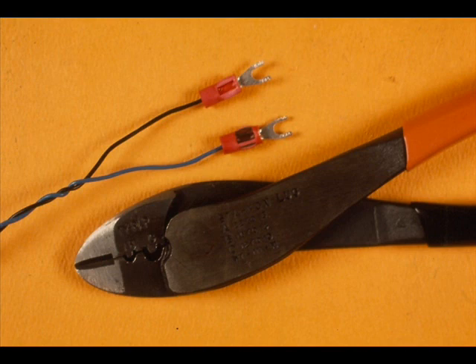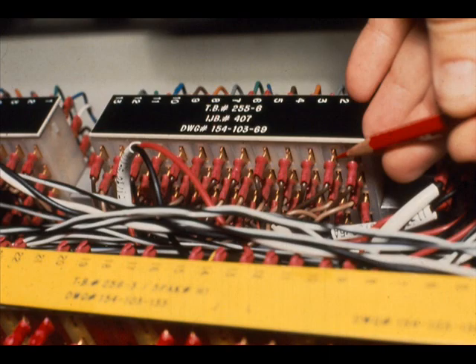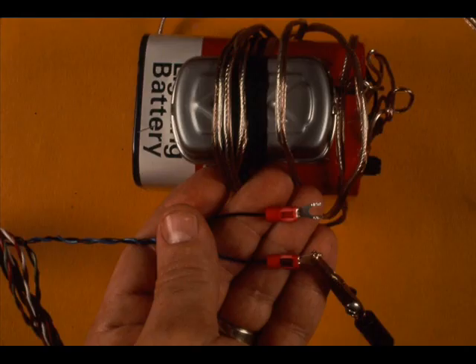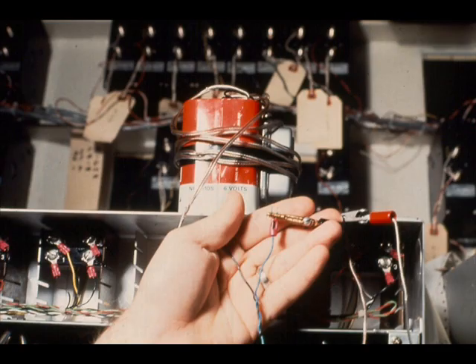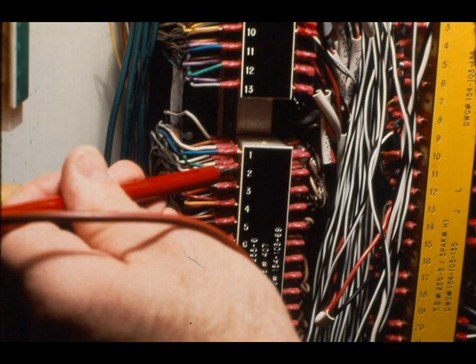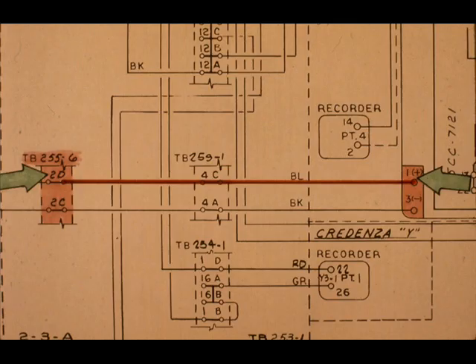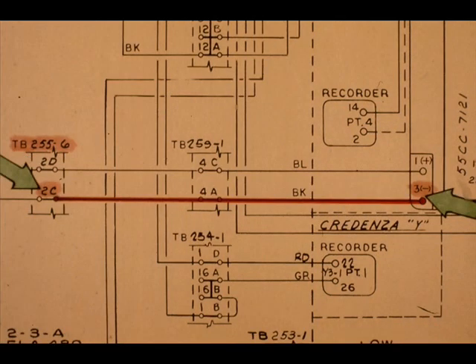Attach the lugs to the cable wire pairs, but do not terminate the cable on the output module yet. Terminate the jumper that connects the transducer block to the field cable block. We will check continuity from the output module to the field cable block by using a buzzer. Hook the buzzer from the blue wire to ground. Ground TB255-6 terminal 2D. This is the electrical path you have checked for continuity. Verify terminal 2C on TB255-6 through the black wire to ground.